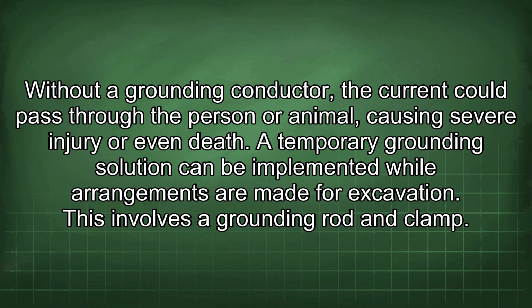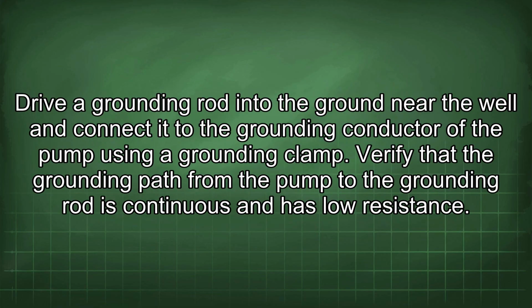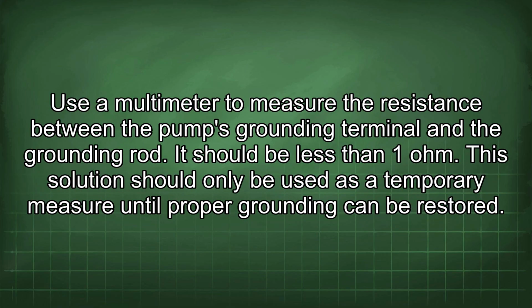A temporary grounding solution can be implemented while arrangements are made for excavation. This involves a grounding rod and clamp. Drive a grounding rod into the ground near the well and connect it to the grounding conductor of the pump using a grounding clamp. Verify that the grounding path from the pump to the grounding rod is continuous and has low resistance. Use a multimeter to measure the resistance between the pump's grounding terminal and the grounding rod. It should be less than 1 ohm.